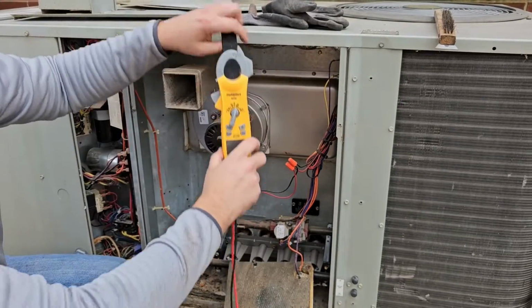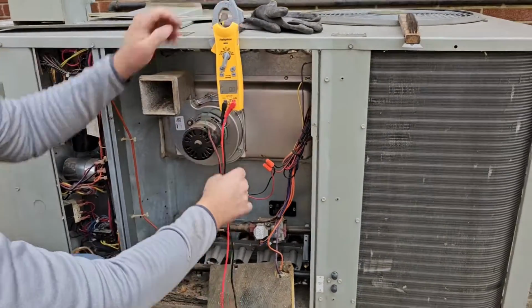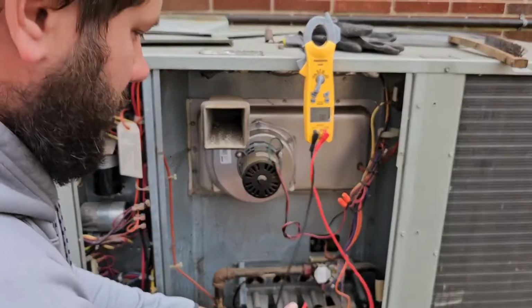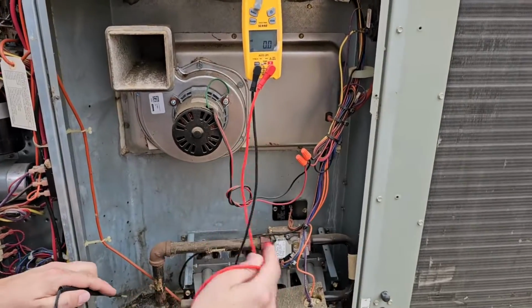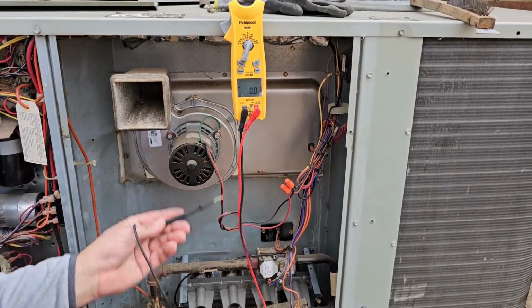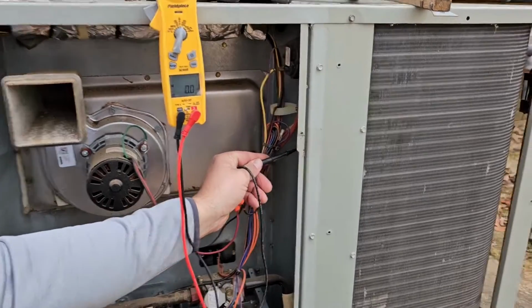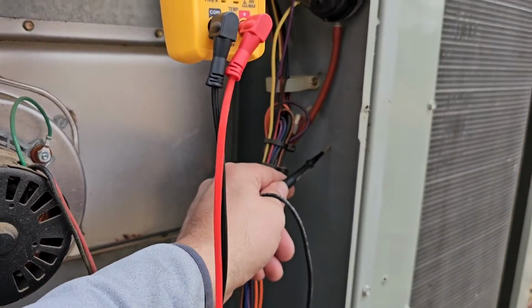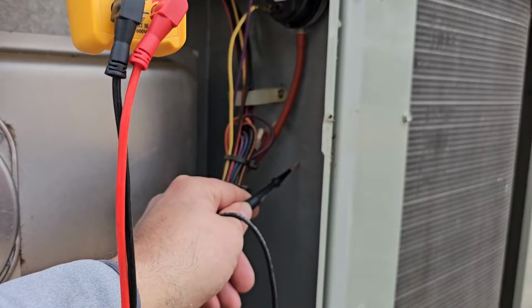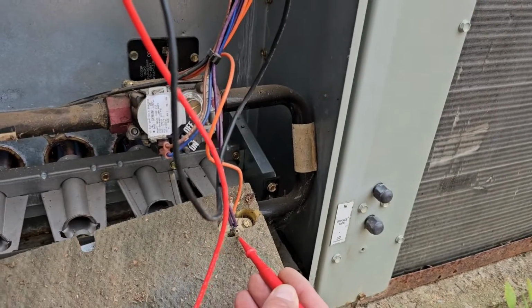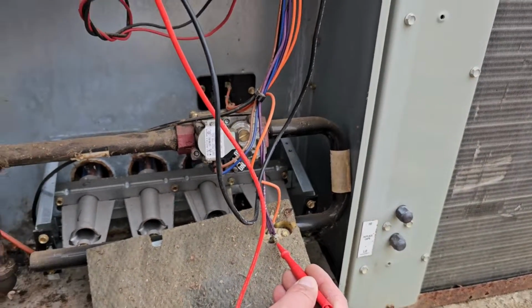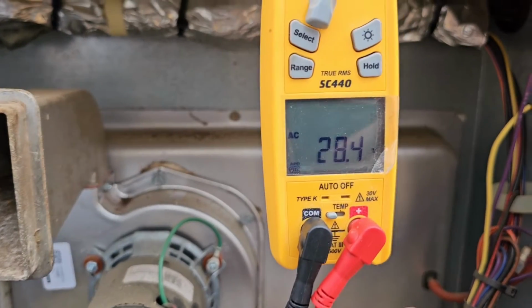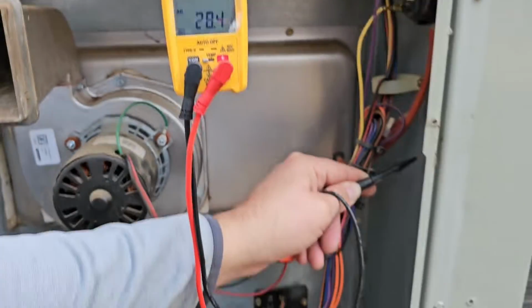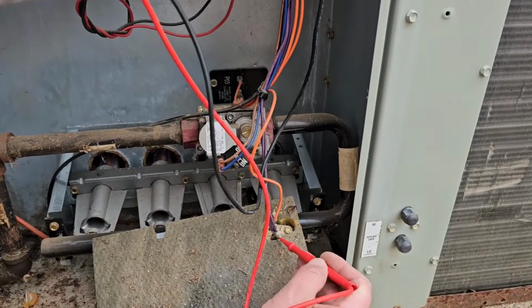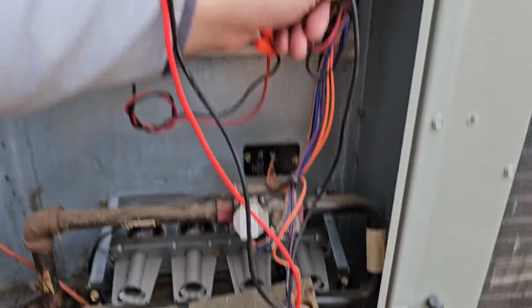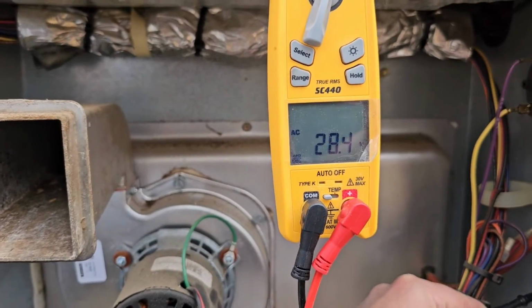All right. See that? Looks like it's lit all the way across. We're going to check one lead to the ground. See that? All right, and then the other lead down here. Check the fusible link first. What do we got? 28 volts. Let's check the other side. See, we're on the purple wire. Now we're going to go to the orange wire. 28 volts. So that switch is closed.